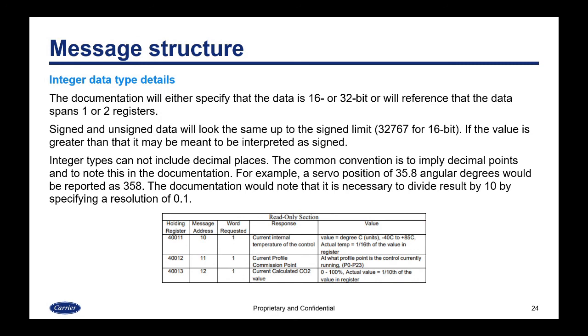The documentation will either specify that the data is 16 or 32-bit, or will reference that the data spans one or two registers. Signed and unsigned data will look the same up to the signed limit of 32,767 for 16-bit. If the value is greater than that, it may be meant to be interpreted as signed or as a 32-bit number. Integer types cannot include decimal places — this is very important with Modbus. The common convention is to imply decimal points and note this in the documentation. For example, a servo position of 35.8 angular degrees would be reported via Modbus as 358. The documentation would note that it is necessary to divide the result by 10, or by specifying a resolution of 0.1.